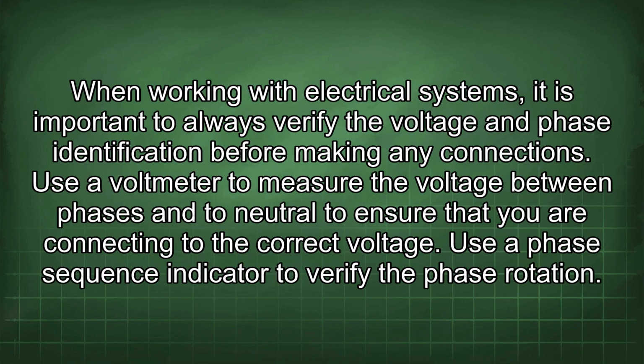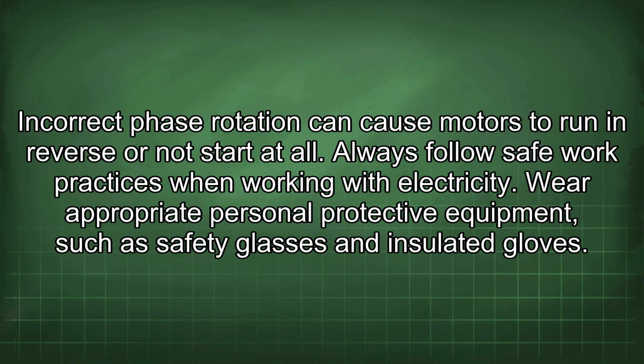When working with electrical systems, it is important to always verify the voltage and phase identification before making any connections. Use a voltmeter to measure the voltage between phases and to neutral to ensure that you are connecting to the correct voltage. Use a phase sequence indicator to verify the phase rotation. Incorrect phase rotation can cause motors to run in reverse or not start at all.